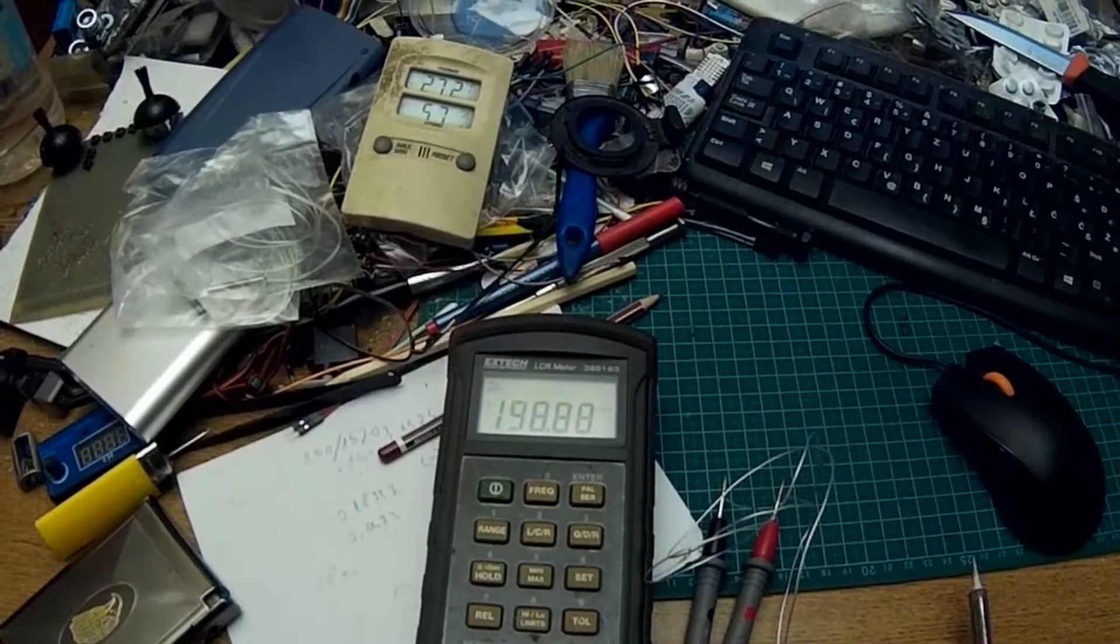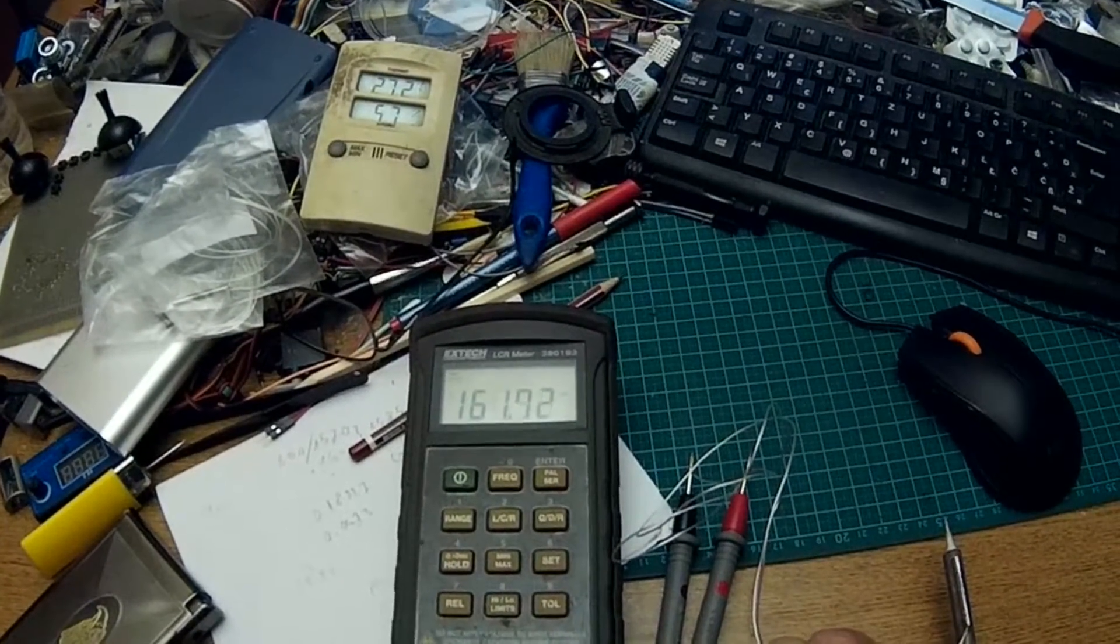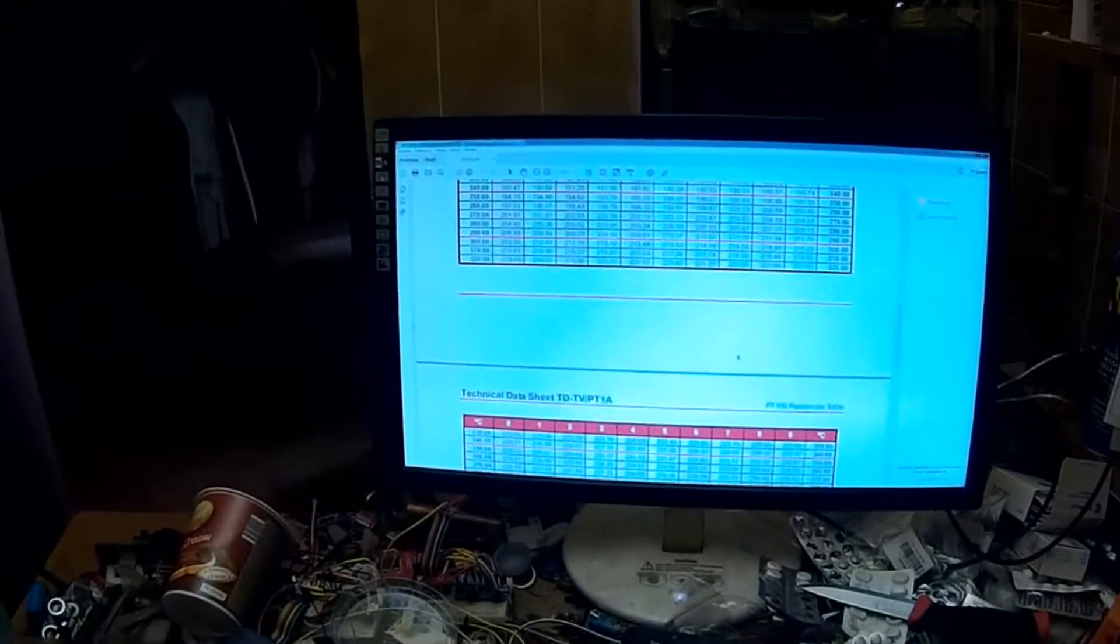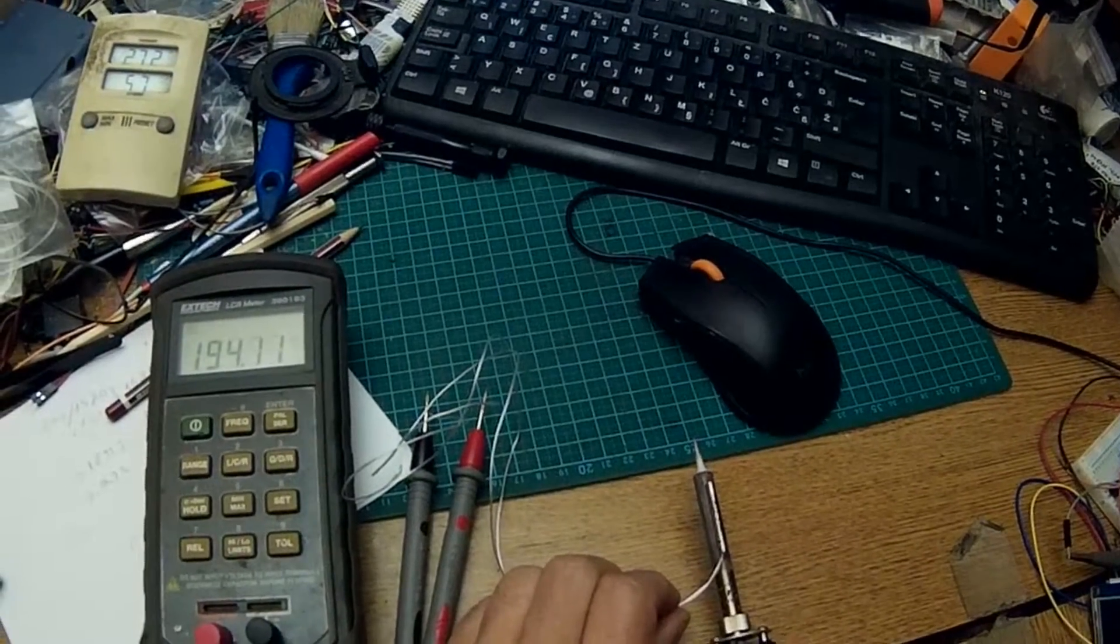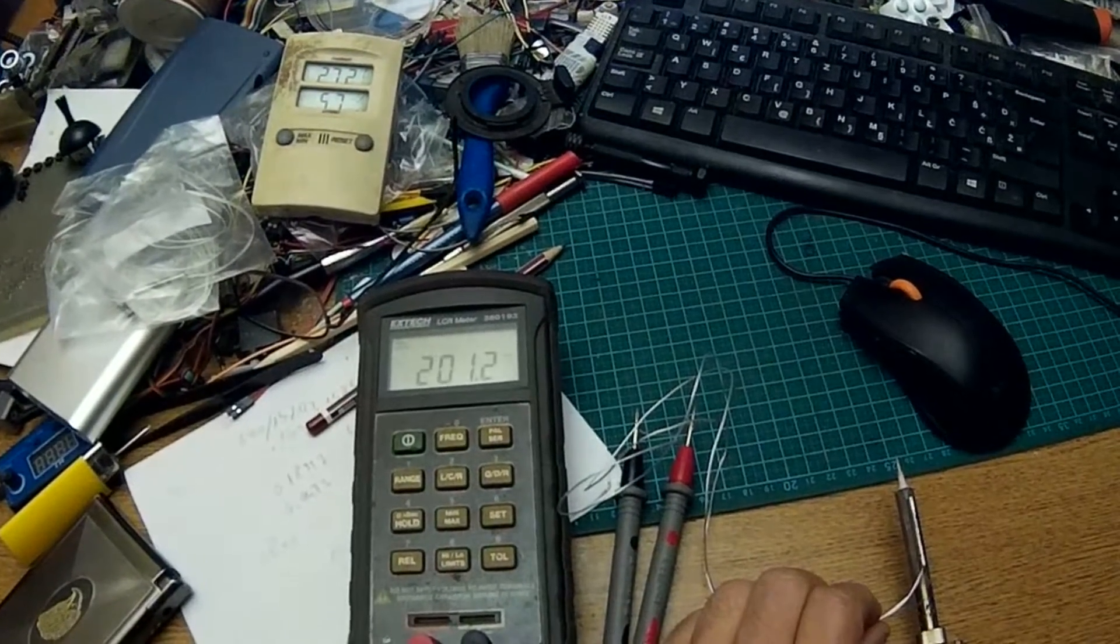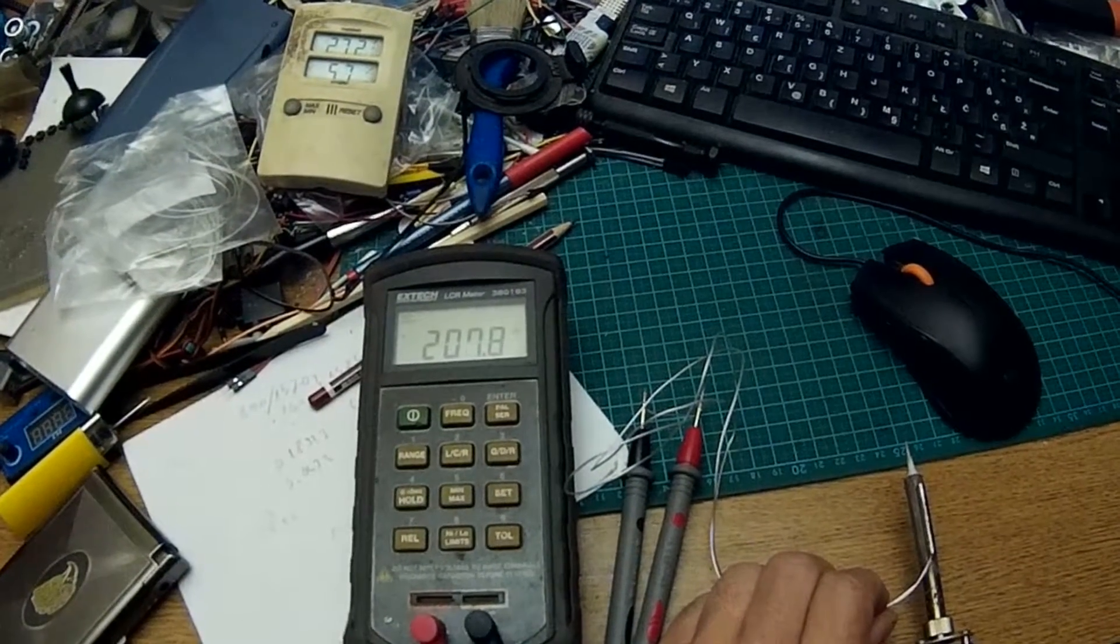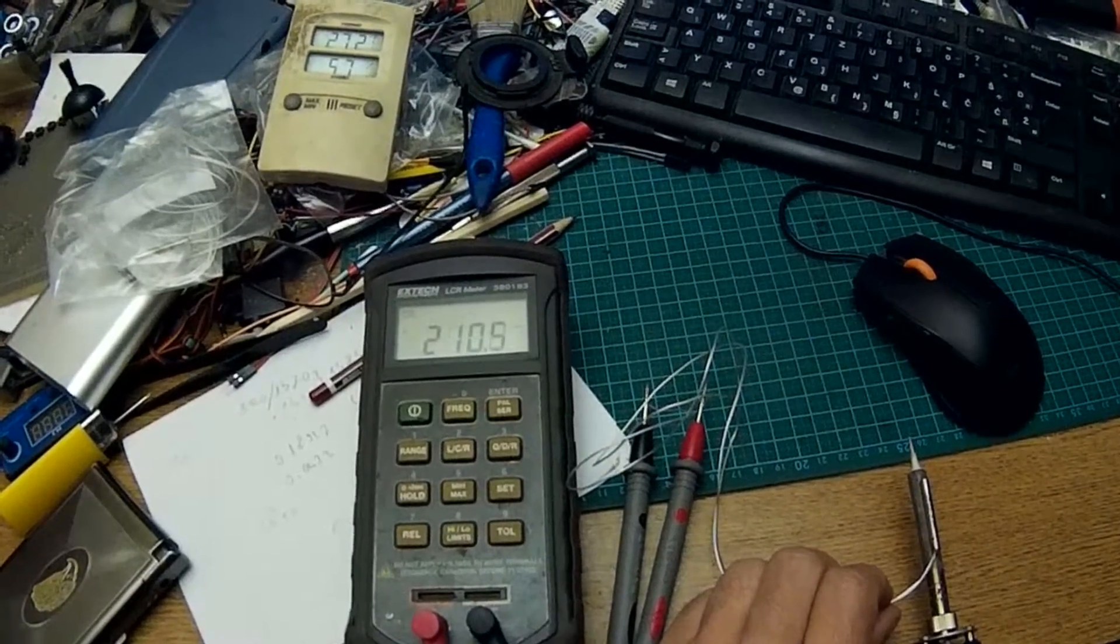Resistance 140, 150, rising... 166, 7, 8, 9. Should be 212 ohms at 300 degrees Celsius, but it is slow due to bad contact between thermal masses. 201, 2, 203, 205, 7, 8, 209, 210.